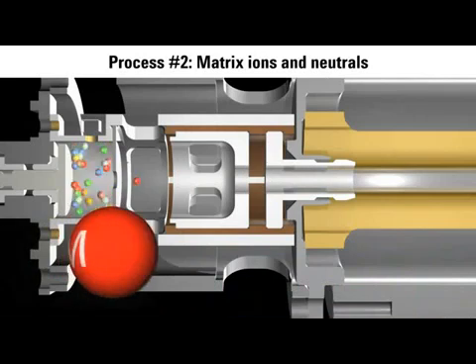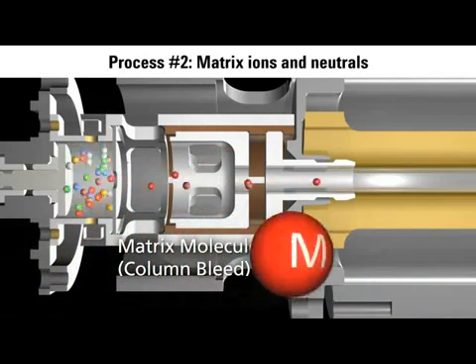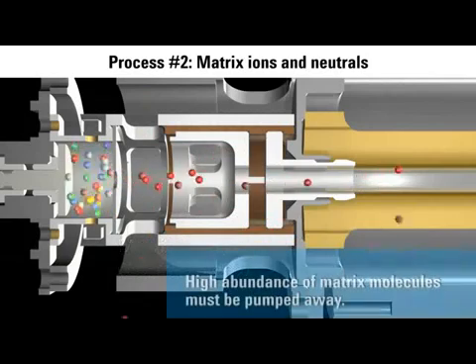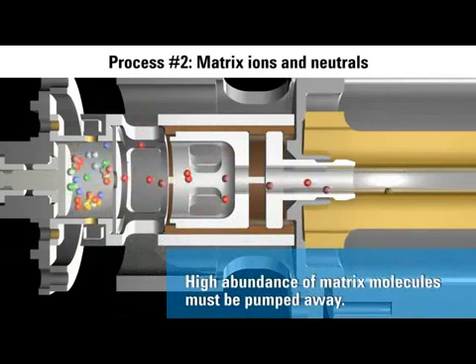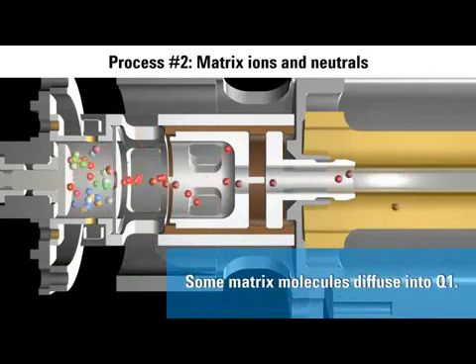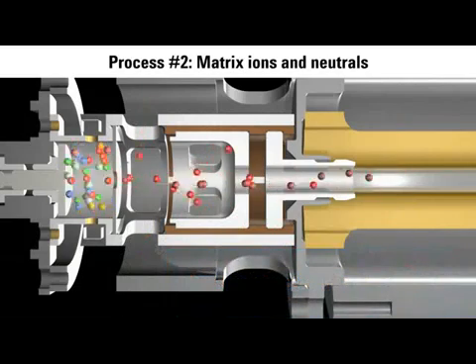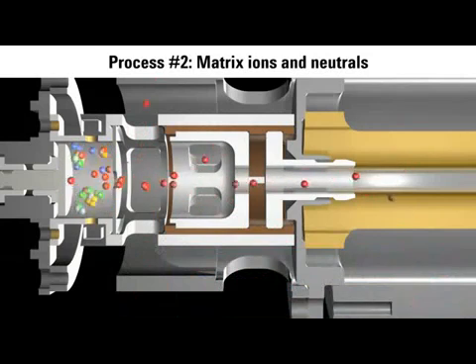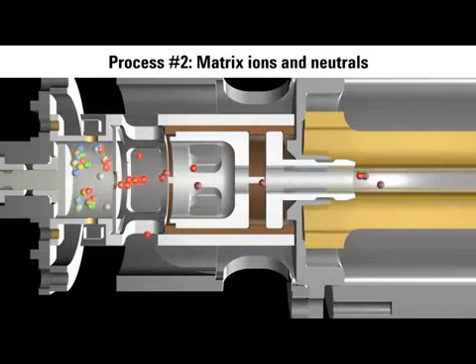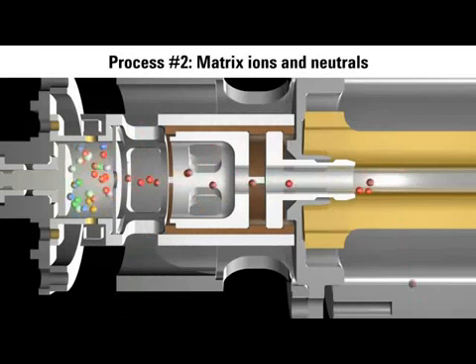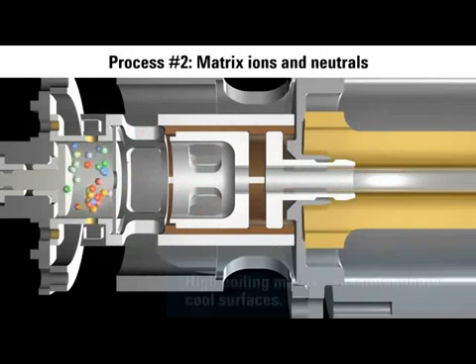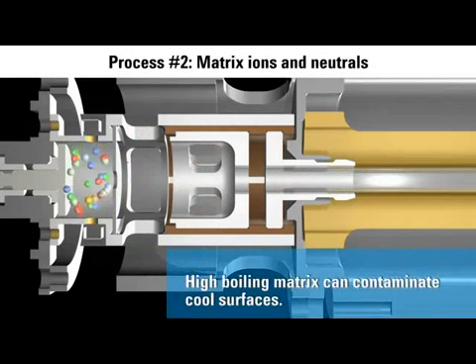Again we ask: what about the large population of non-ionized molecules? Although the turbo pump removes many neutrals quickly, some will randomly diffuse into the quadrupole. At the end of the GC separation, the EI source will be flooded with the highest boiling molecules from the sample matrix. Even in a vacuum, these high-boiling molecules can contaminate surfaces in the mass spectrometer.